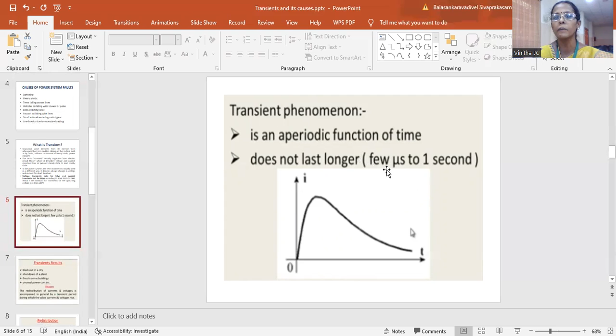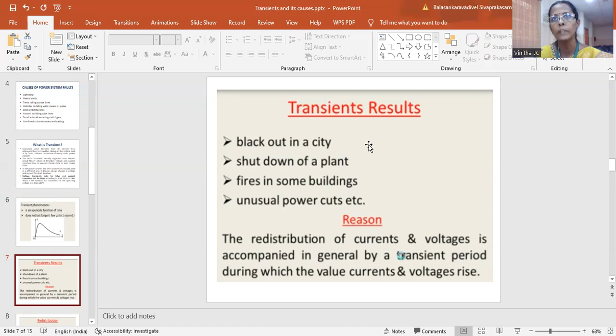So why do these transients occur, and what will happen if transients persist for a longer duration? These transients are created due to the presence of inductances as well as capacitances in the circuit. Both are energy storage elements that store energy during normal condition. Whenever the switches or circuit breaker contacts are opened, immediately the charge in the capacitance starts to discharge. Due to this charging and discharging of the inductances and capacitances, transients are created, and they exist until the entire energy stored in the capacitances and inductances is damped out.